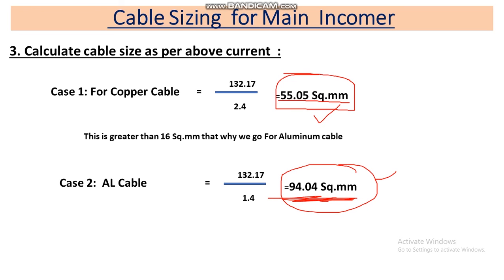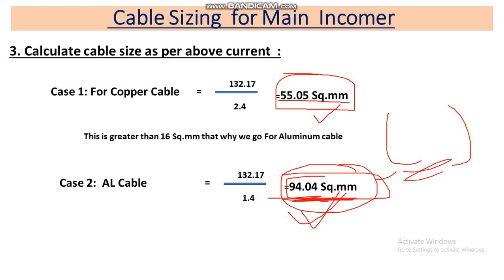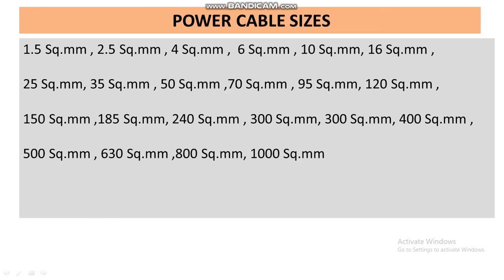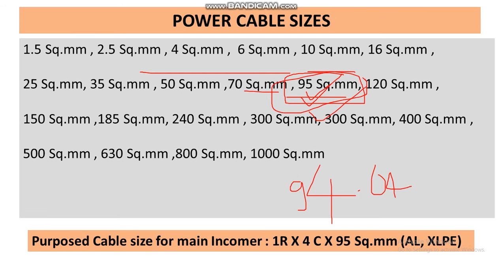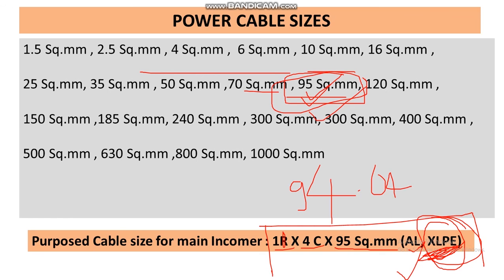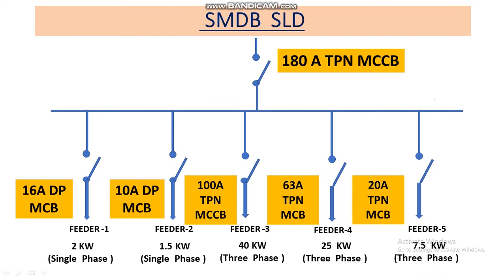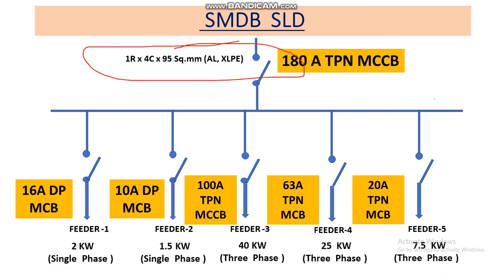Our calculated aluminum cable size is 94.04 square mm. We always go for a higher value, not below the calculated value. Looking at the cable selection chart, 94.04 is near 95 square mm. So our final proposed cable size for the main incomer is: 1 run, 4-core, 95 square mm aluminum XLPE insulation cable. This is the cable selected for the main incomer.